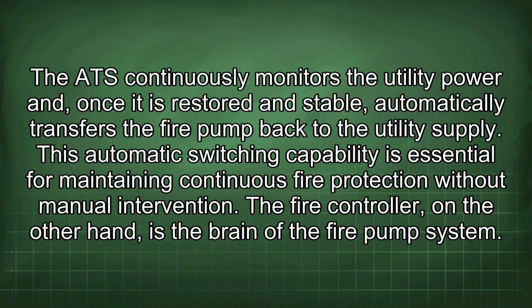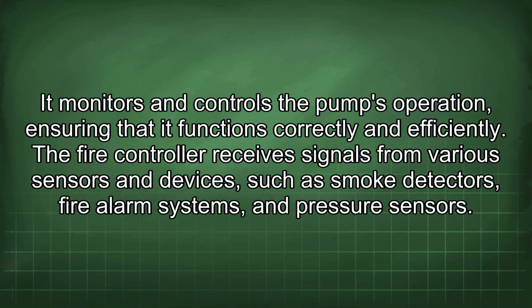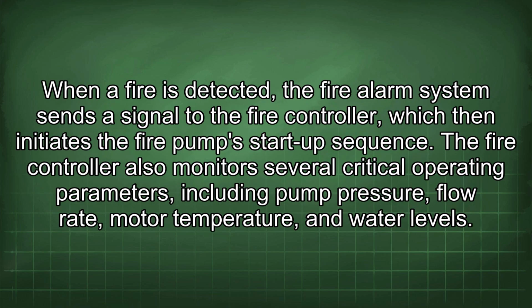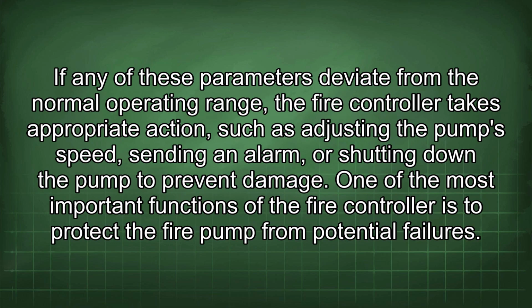The fire controller, on the other hand, is the brain of the fire pump system. It monitors and controls the pump's operation, ensuring that it functions correctly and efficiently. The fire controller receives signals from various sensors and devices such as smoke detectors, fire alarm systems, and pressure sensors. When a fire is detected, the fire alarm system sends a signal to the fire controller, which then initiates the fire pump startup sequence. The fire controller also monitors several critical operating parameters, including pump pressure, flow rate, motor temperature, and water levels. If any of these parameters deviate from the normal operating range, the fire controller takes appropriate action, such as adjusting the pump speed, sending an alarm, or shutting down the pump to prevent damage.